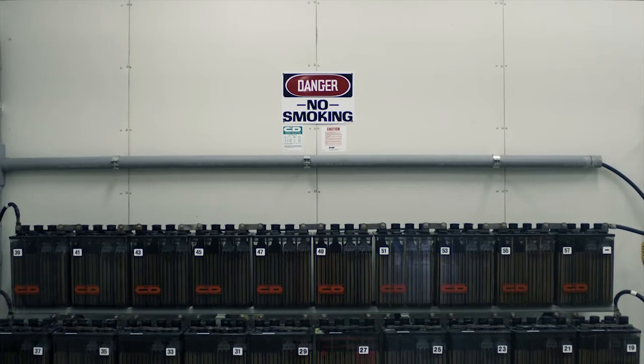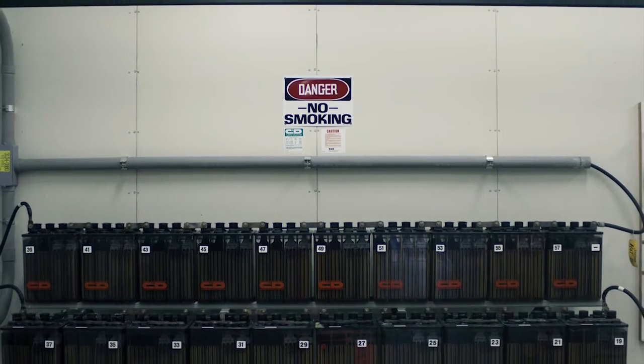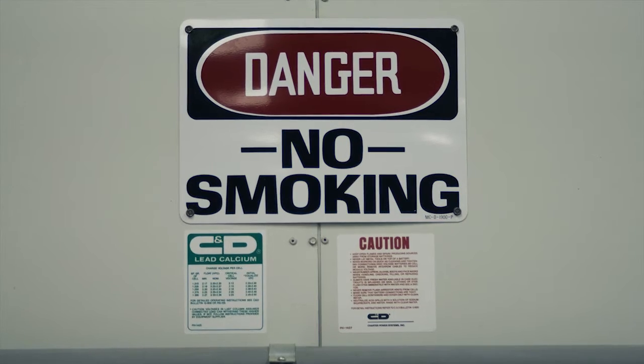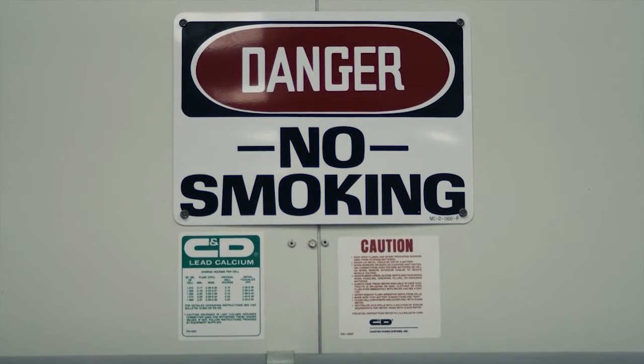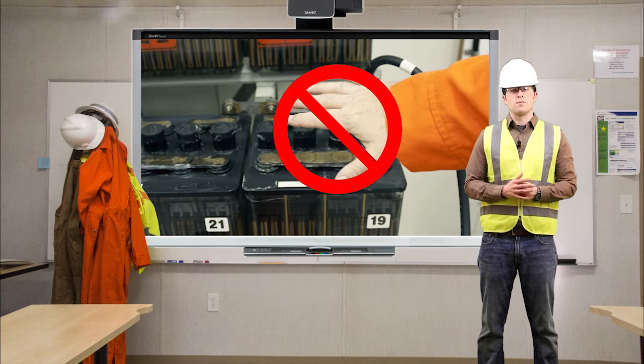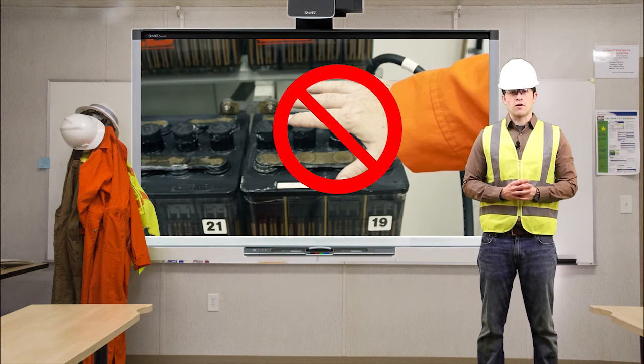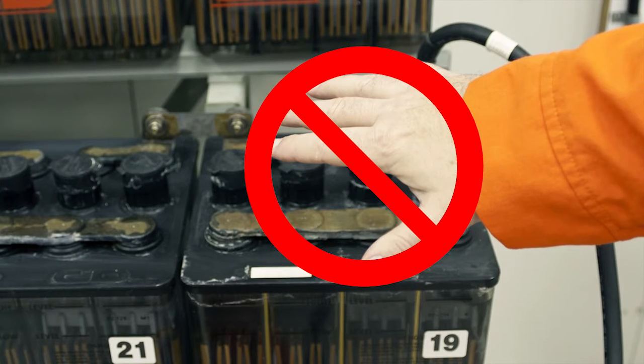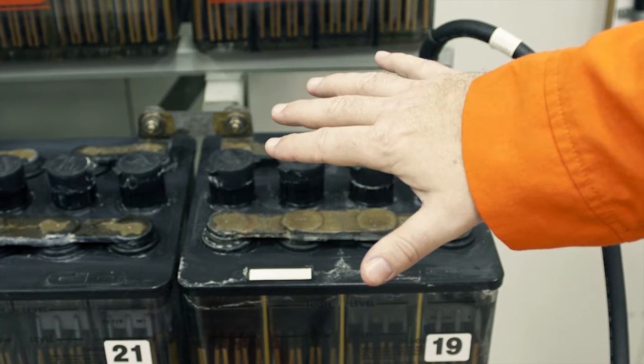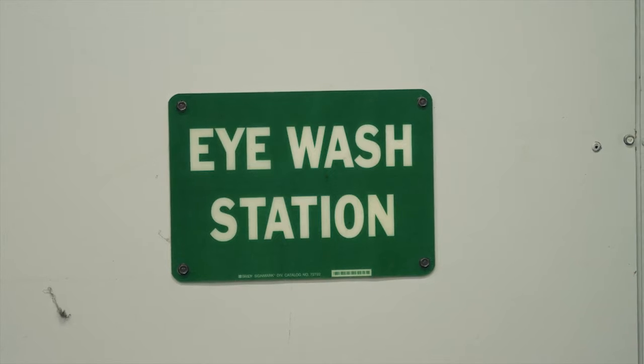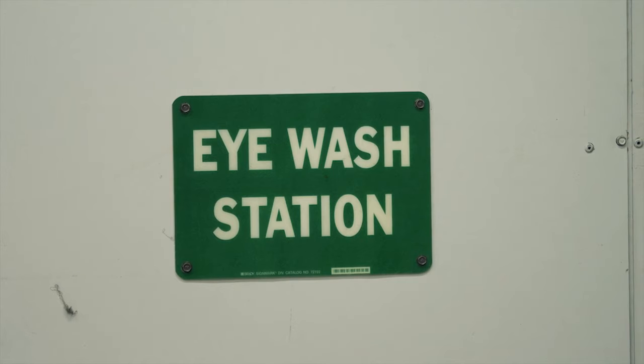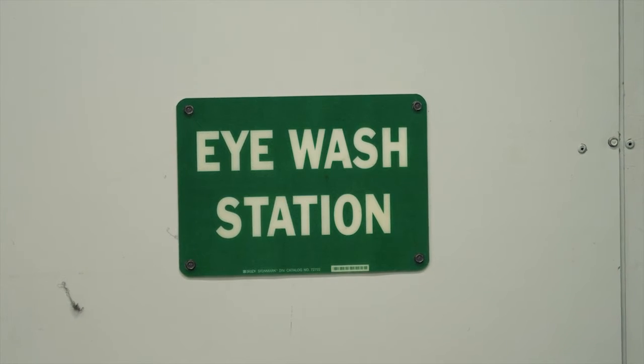When batteries are charging, they produce a highly explosive hydrogen gas. As a result, smoking is not allowed inside the control house. Avoid contact with batteries unless you are authorized to work on them. If your work requires you to be in close proximity to batteries, make sure to note the location of the eye wash station in the event of contact with battery chemicals.